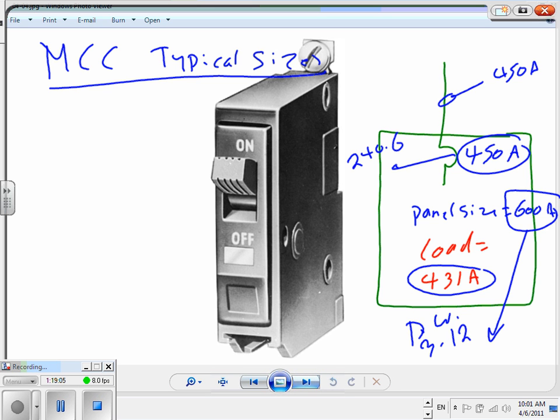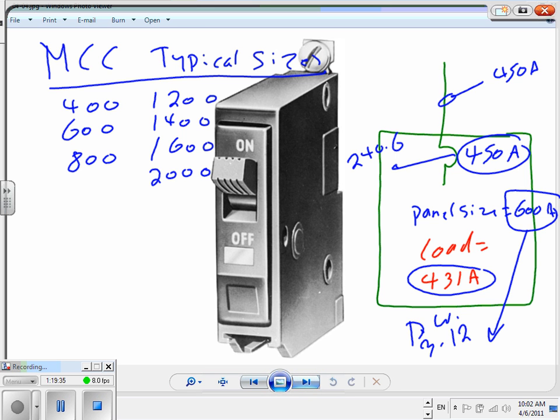Here are the sizes that I have, guys. I always put them in 3-13. So I have 400, 600, 800 standard sizes, and then 1200, 1400, I believe, 1600, 2000, 2500, 3200, and 4,000. These are typical standard MCC sizes.